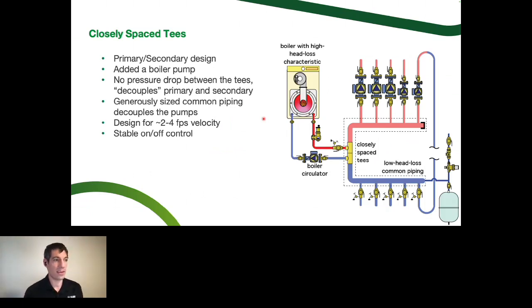So closely spaced tees is the time-tested, least expensive purchase price way to do primary secondary correctly. It absolutely will work. I've got some nuances on the next slide for things to be careful with, but closely spaced tees will absolutely do the job. If you've got a closely spaced setup, where inside, if you could measure it with a little flow meter right in the center there, the velocity is less than 2 to 4 feet per second, you're in good shape. You've got a scenario where this gear can spin at a different speed from this gear over here. It's going to work for you.